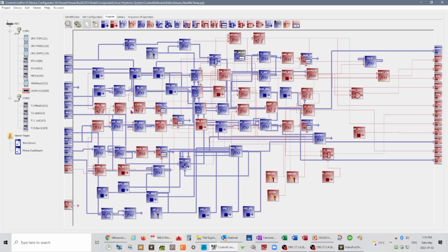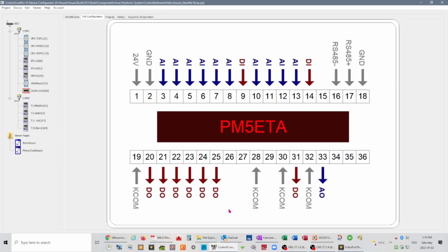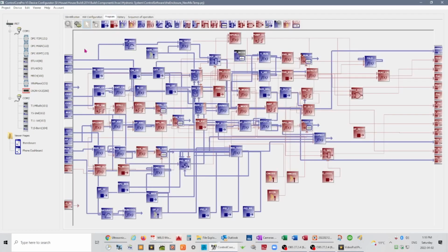So this is the programming screen for the DX2W from ThermAtlantic. On our left, we have all of the inputs, and on our right, we have all of the outputs. These were what was defined in the terminals here. For each terminal, we defined what type of output it was, and then that shows up on each side of the program screen. All of this is blocks that have been selected from the available blocks above and added to create the program between reading the inputs and acting on the outputs.